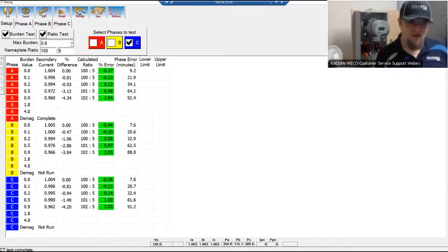Earlier on, I threw a demag on the A phase CT. If you decide to run the demag, as I said earlier, it will tell you if you have run a demag on that test. It'll say demag complete on my A phase, as you can see down there. And then B and C, I did not run on those two CTs. If you like what you're seeing and you want to save this, right up at the top, there's a save button. If you hit save, it'll save these results into the RW, and then you can retrieve those at any time later on in administration under CT test.